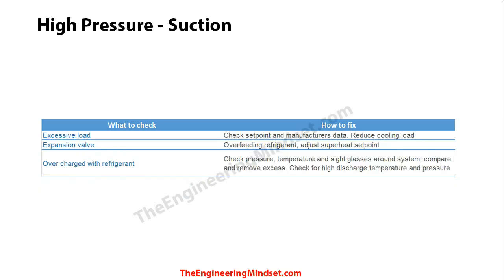For high pressure on the suction line, there are three main causes. The first is excessive load — the cooling load is simply too much for the chiller, so reduce it or spread it across other chillers and cooling equipment. The expansion valve may also be overfeeding refrigerant as it starts to fail — try adjusting the superheat set point first, then replace the valve if needed. Finally, the system could be overcharged with refrigerant; check pressures and temperatures and remove the excess if that's the cause.